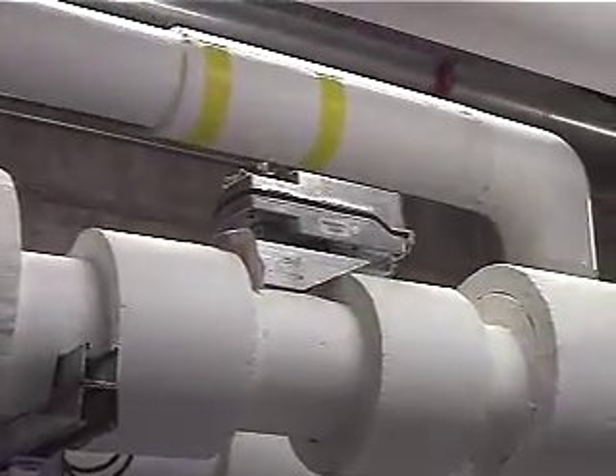Well, that would be the case, but like Kevin was saying here on these valves right here, these should be a slow-acting ball valve. And I didn't supply the ball valve, so I don't know what was supplied, but if these are fast-acting, they will be slammed shut. There's going to be a pressure spike right in here that could cause that relief valve to pop open. So the recommendation would be to check and see what these are, and these valves right here, to make sure they're slow acting. And if they are fast acting, see if you can slow them down, because that could be why that popped off.